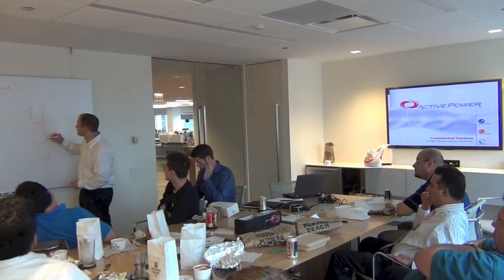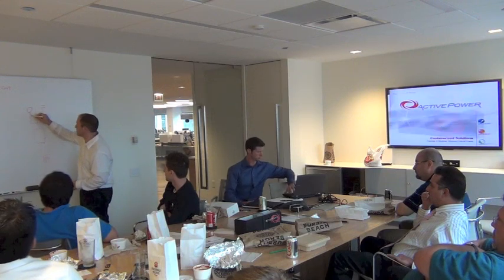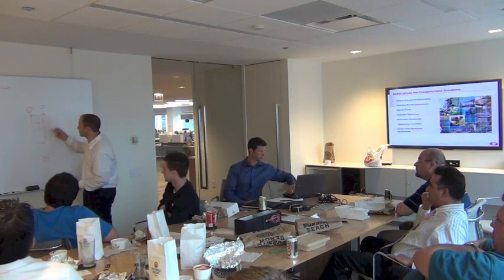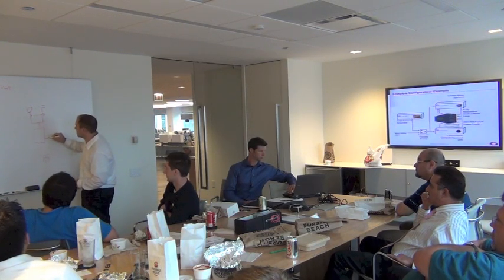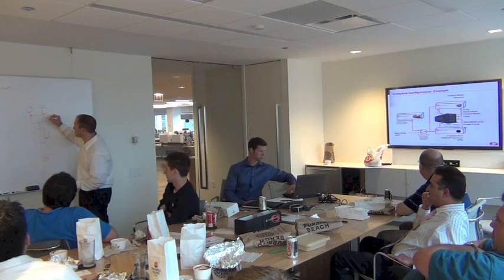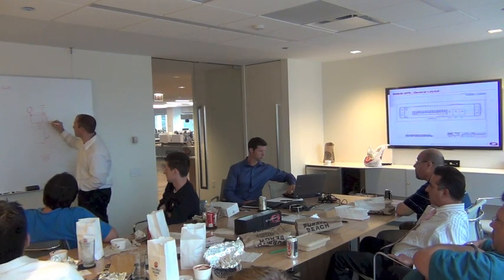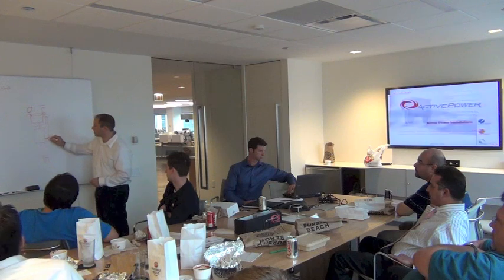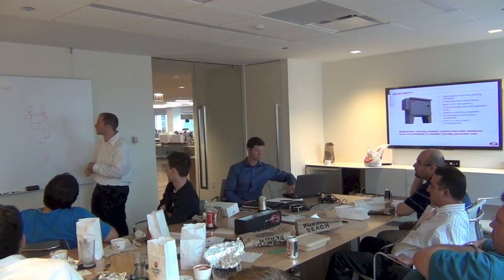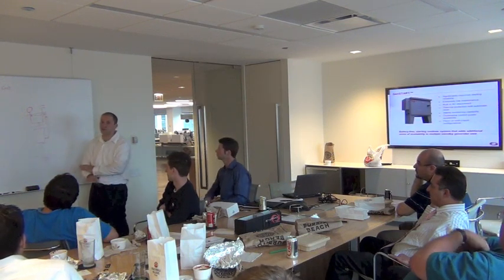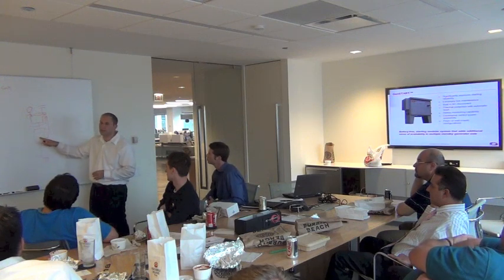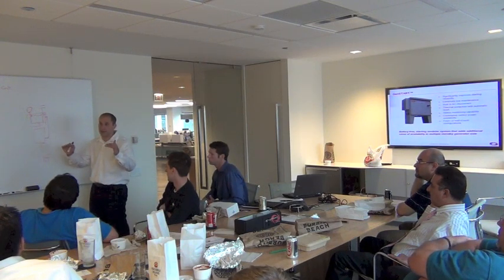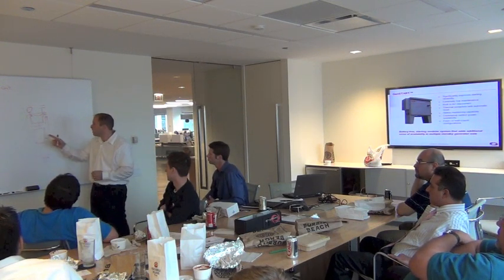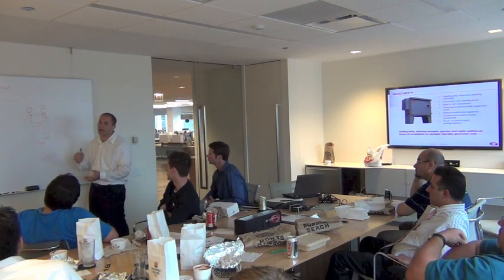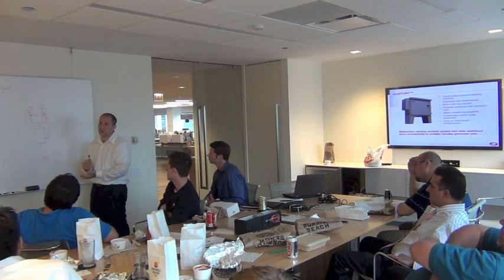And what that does is, whether you're using a breaker pair versus a transfer switch, either one is fine. Basically, what ATS command does is just a couple of 18 gauge wires that wire back to your gear. It's a programmable feature. So if your switchgear, your breaker pair or transfer switch, doesn't transfer for any reason, and this UPS is in discharge and the flywheels get down to a certain percent energy, let's say 85%, we'll send a signal to your transfer switch or switchgear to say, hey, for whatever reason utility's unstable, you haven't transferred, send a start signal to the generator, we're going to transfer to generator.